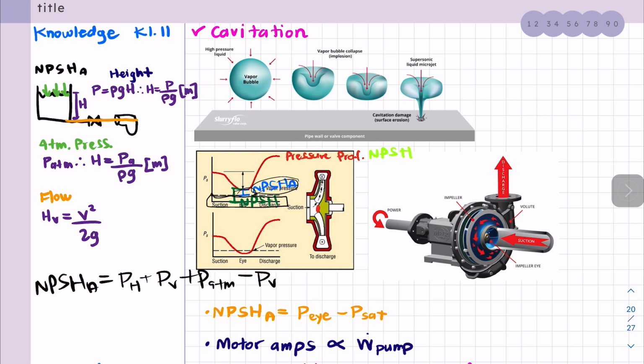So cavitation is a leading cause of many problems in fluid systems, and it can reduce the efficiency. It can increase vibration, noise, and damage the equipment. It can also cause erosion in a pump impeller, for instance, which can reduce the life of the pump and increase maintenance costs. Cavitation is often caused by a combination of factors, including high fluid velocity, low pressure, and the presence of impurities in the fluid. So it is more likely to occur in pumps that have low net positive suction head values.